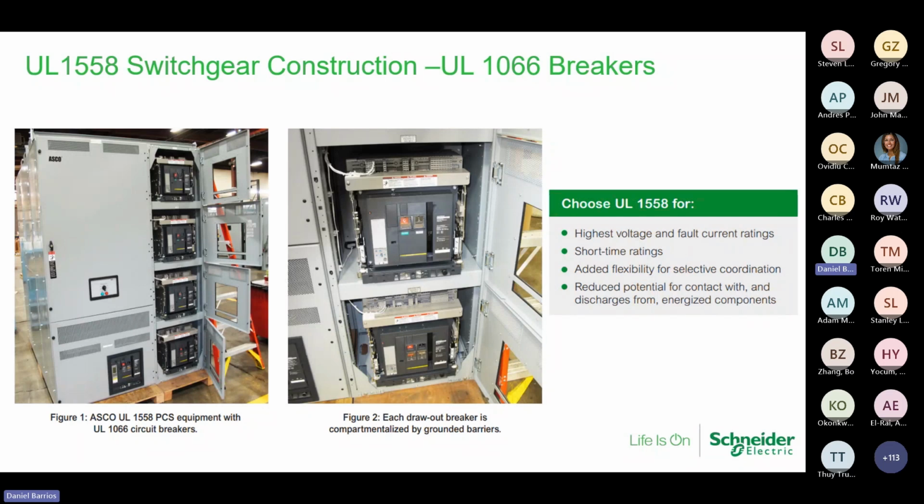We can also do 200K bracing or such. If you do this also and you have all of your breakers this way, you may open yourself up much more easily to selective coordination. That is part of the things that is pointed out on that little chart that we've alluded to a few times.